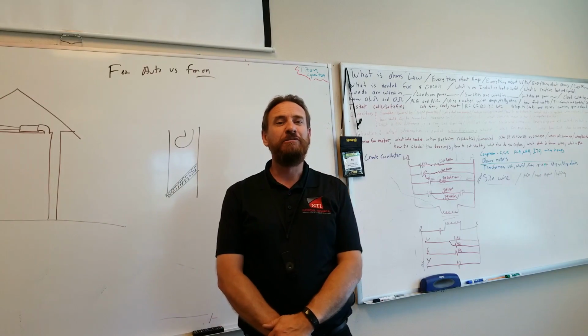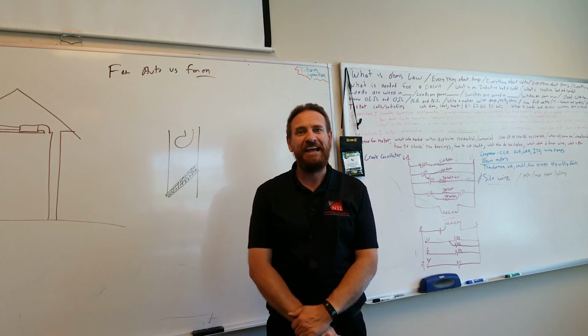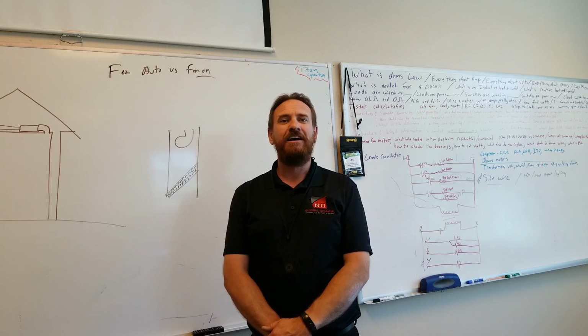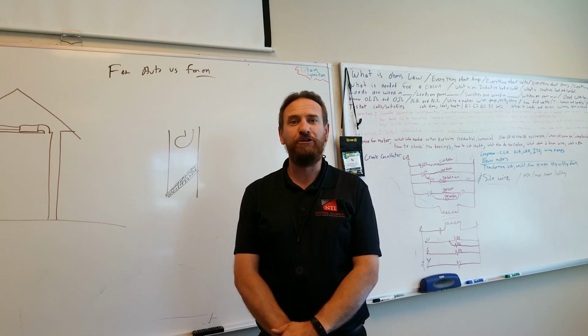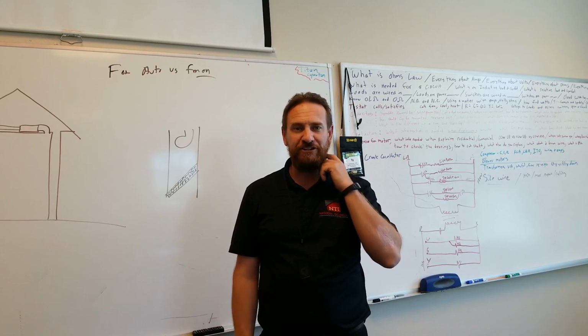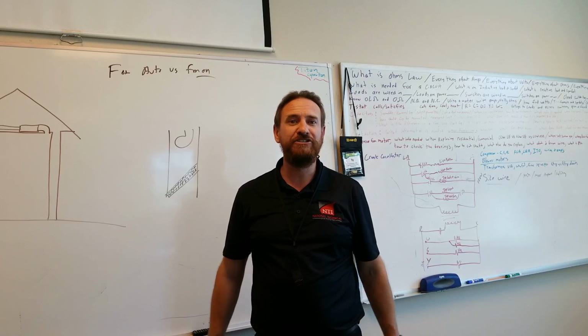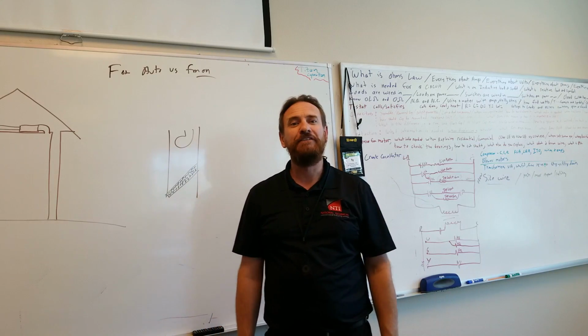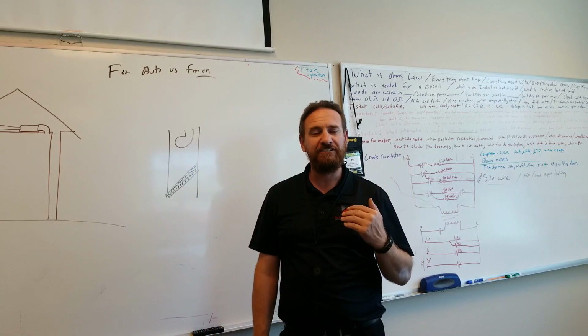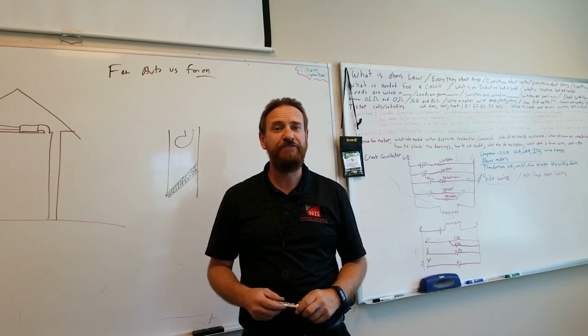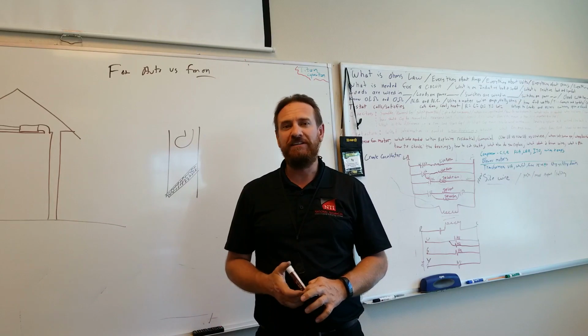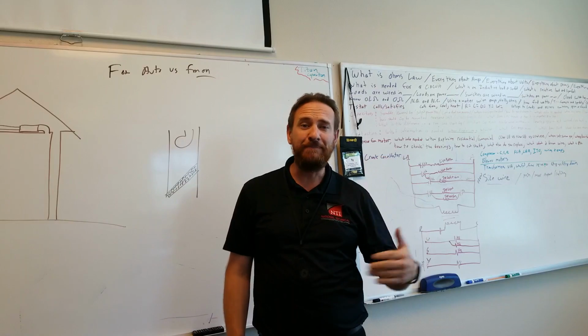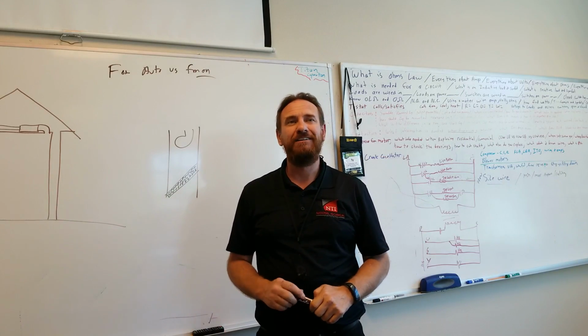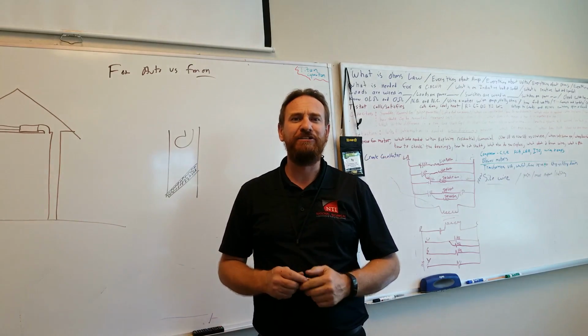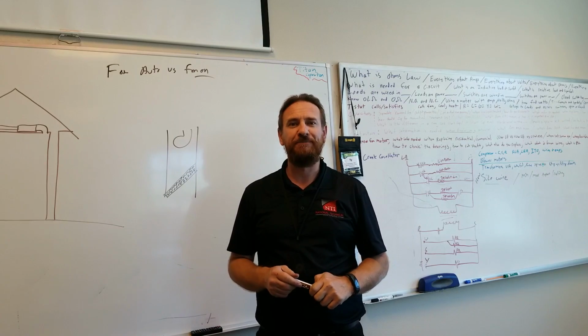Some of the new motors are ECM, X13, variable speed, constant velocity, or constant torque motors. These motors are a lot more energy efficient. It's going to use a lot less energy to move that same amount of air. And when you leave the fan on, it runs the fan constantly at a lower speed. So it's a lot more energy efficient to do that. So with the new ECM and variable speed motors, you can keep the air moving for a very small amount. It's like running a 60-watt light bulb, just an approximation.